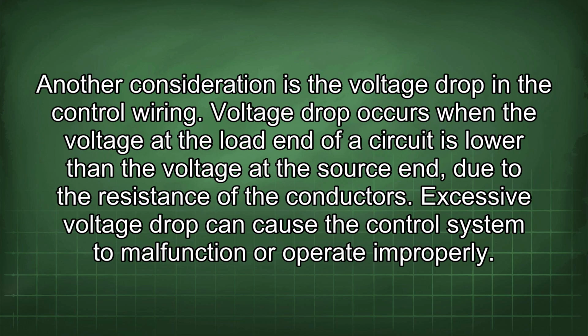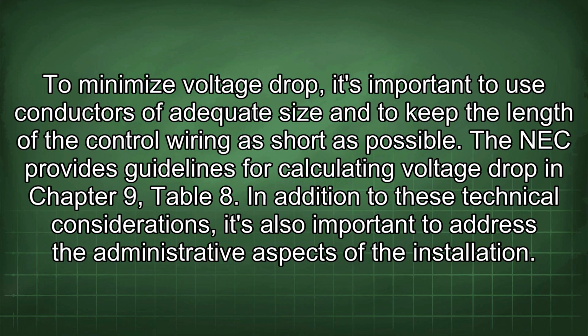Another consideration is the voltage drop in the control wiring. Voltage drop occurs when the voltage at the load end of a circuit is lower than the voltage at the source end, due to the resistance of the conductors. Excessive voltage drop can cause the control system to malfunction or operate improperly. To minimize voltage drop, it's important to use conductors of adequate size and to keep the length of the control wiring as short as possible. The NEC provides guidelines for calculating voltage drop in Chapter 9, Table 8.